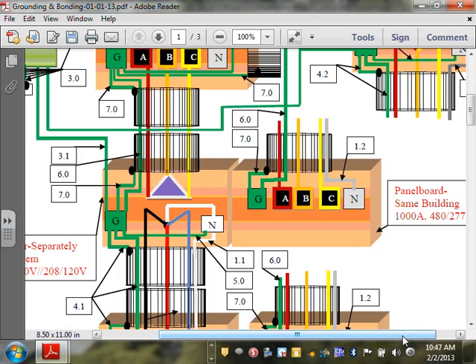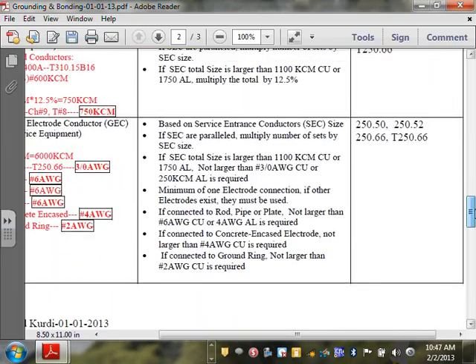If you bond the neutral here, that's bad news. We'll talk about why it's bad news later on. So we bonded these together. Let me just go to number 6, guys, on sizing number 6. Now remember, I have a 1,000 amp feed circuit breaker sitting right here, feeding a 1,000 amp panel board. So I'm sizing for a 1,000 amp panel board. So if you go to number 7 all the way down, you'll see how we size that one, making it easier.